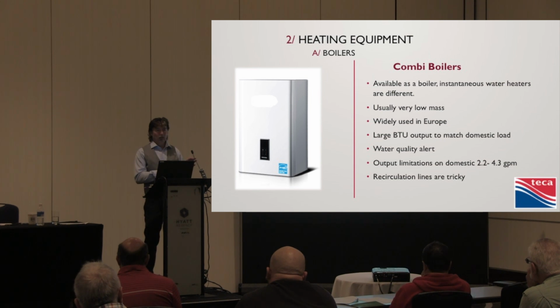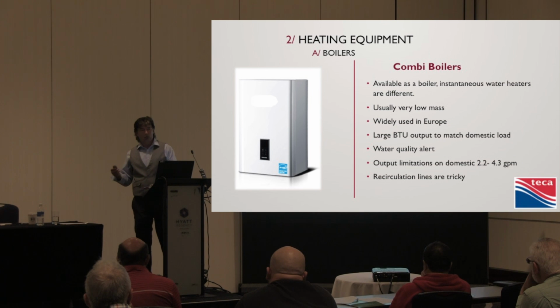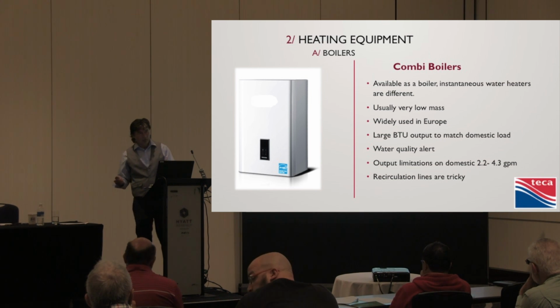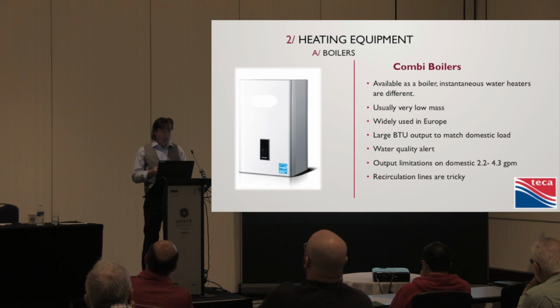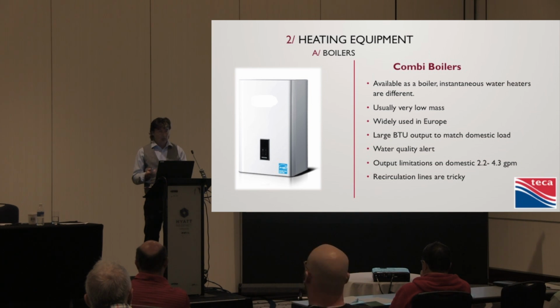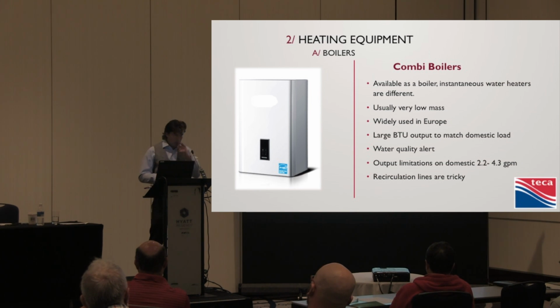And so you go to put that in your home, it's going to have that capacity. Even though your heat load is 53,000 BTUs, you're still having to put that in because what you're doing is heating water instantaneously. You take water from 50 degrees Fahrenheit and raise it to 140, which the plumbing code says you have to do, and that takes a lot of BTUs. You have only one kick at the cat. So that heat exchanger is large, it's very fine, and you're devoting all of that 180,000 BTUs to heating water instantaneously. Bigger gas lines, that sort of thing.